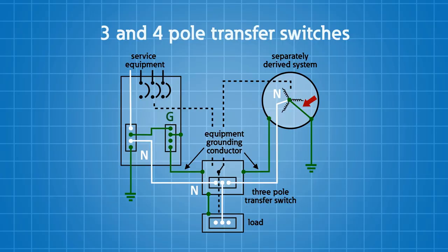But what if I accidentally bonded the neutral to the ground in the generator and I only have a three-pole transfer switch? How do I fix it? Do I have to buy a four-pole transfer switch? Sure you could, or you could simply unbond the neutral in the generator.